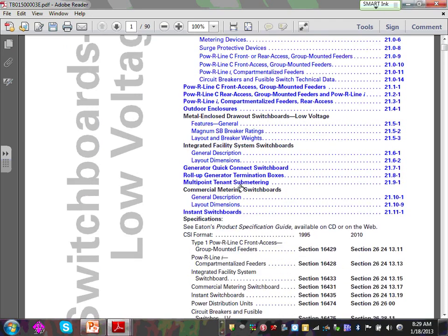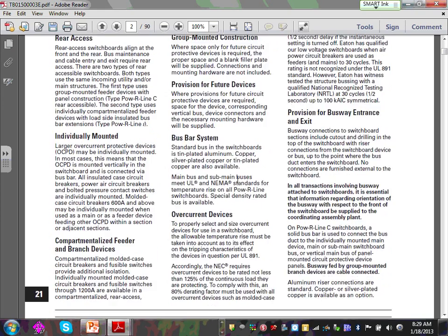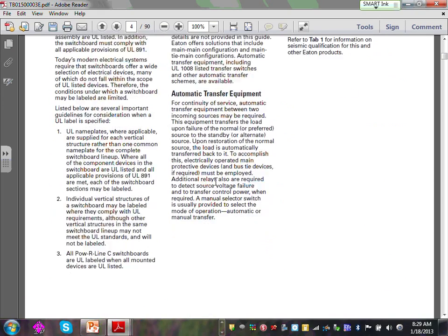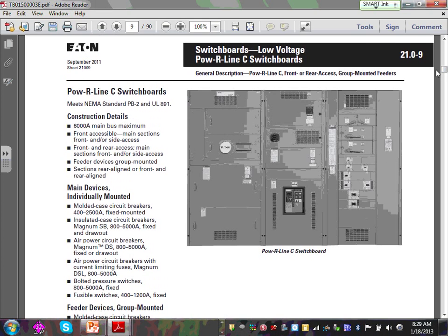So here's my switchboard. Now we're getting into a bigger construction, a standalone in the middle, with bigger circuit breakers, guys, that you can use with them. So here's the design that you're looking at. Everybody can see that? Now that's called the switchboard design. These can be standalone right in the middle of a room. When do you specify something like this, Darren? If you have higher than 1200 amps, 1600 amps, right? Anything higher than 1200 amps, here's your baby. Switchboard. Can I have thumbs up, Chad?